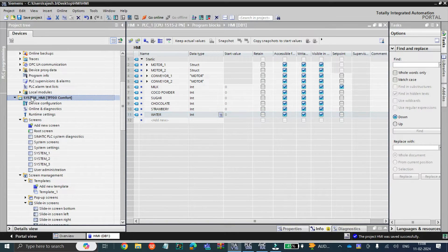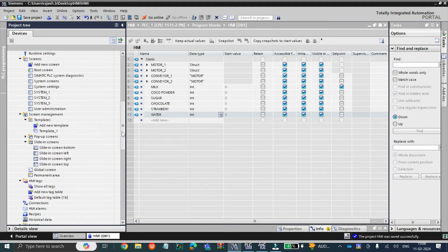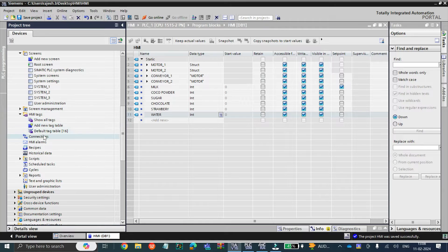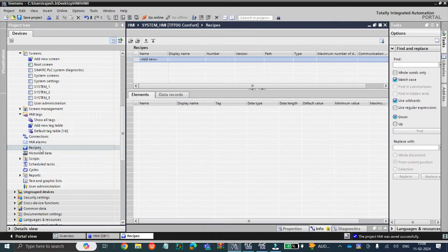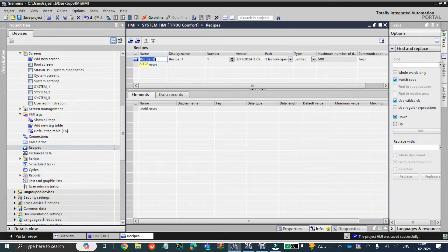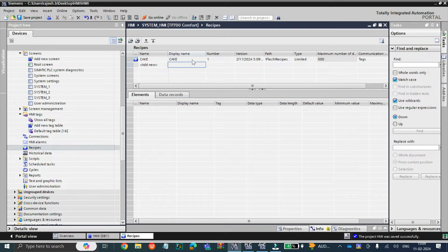To do so, go to the HMI project and close all the windows. In the HMI project, you can see there is an option called recipe — just double click on it. Here you can see it is asking for the recipes. In a single project you could have more than 10 to 15 recipes also, but now we are going to take only one recipe. Let's give the recipe name as 'cake'. This is the name, and this is the display name — what name needs to be displayed. I am also putting the name as 'cake'. Recipe number is one; version, path, everything is mentioned here.